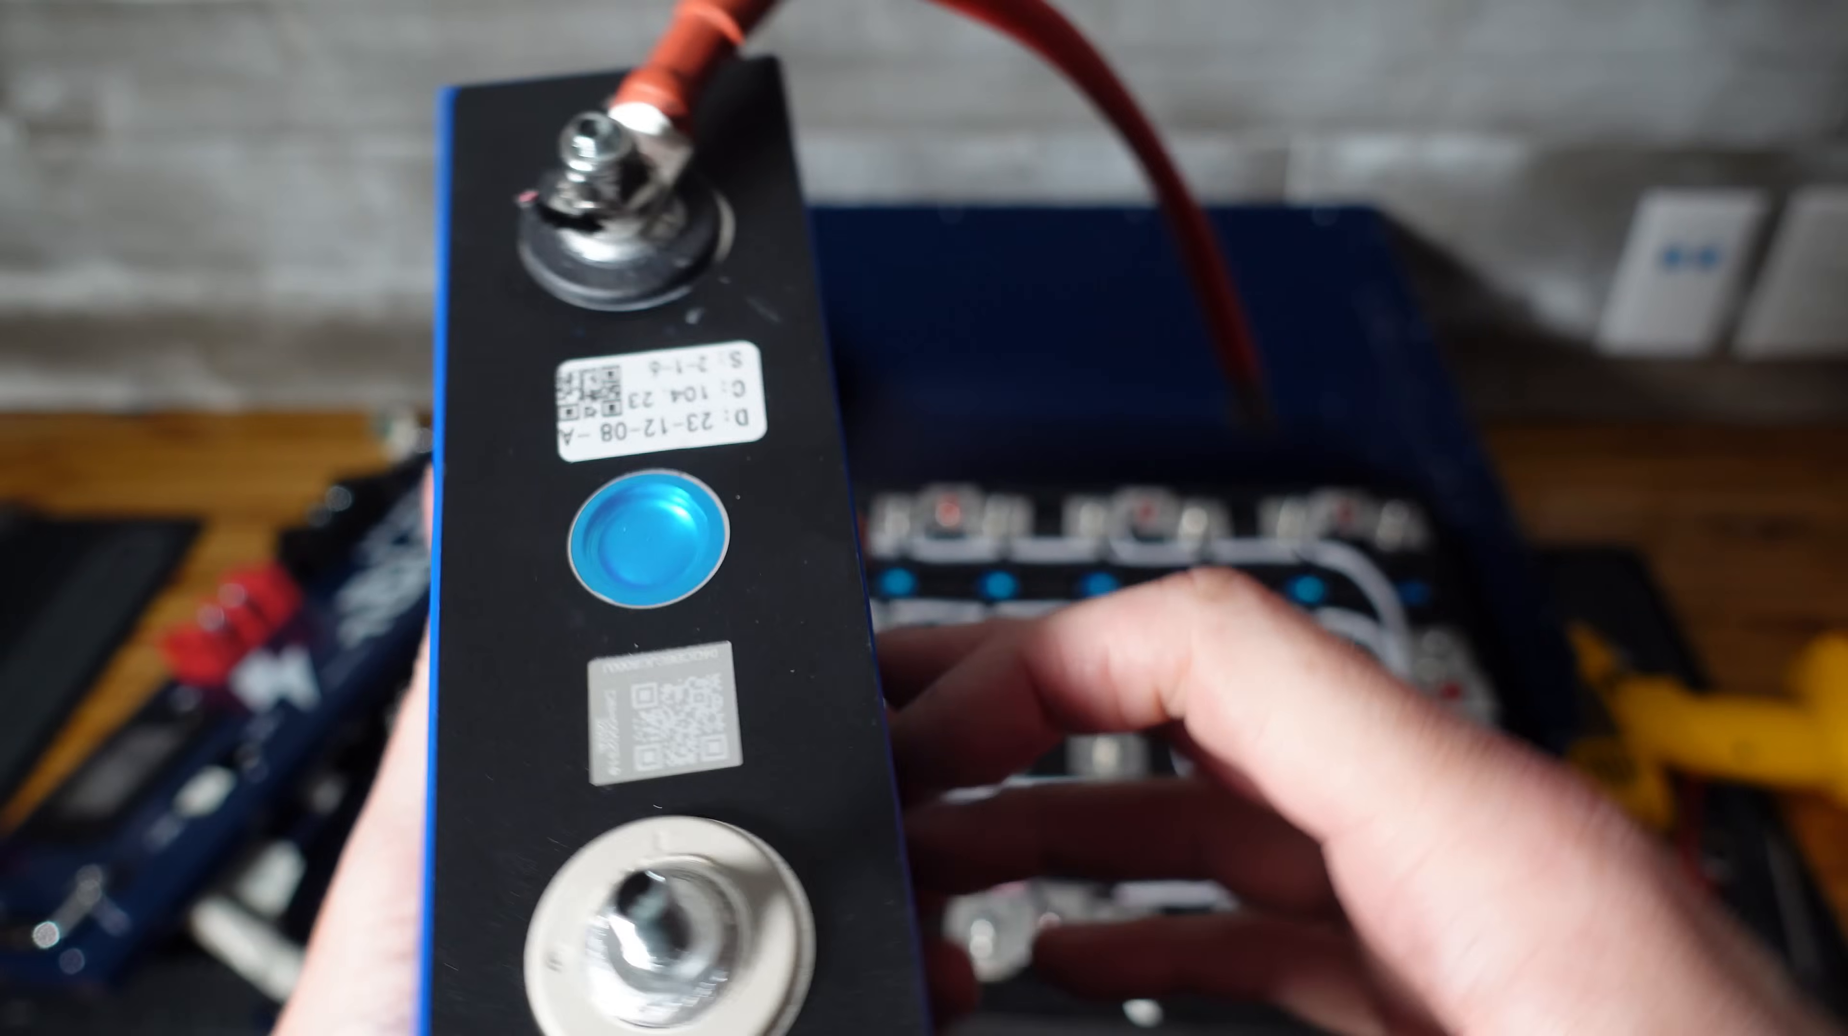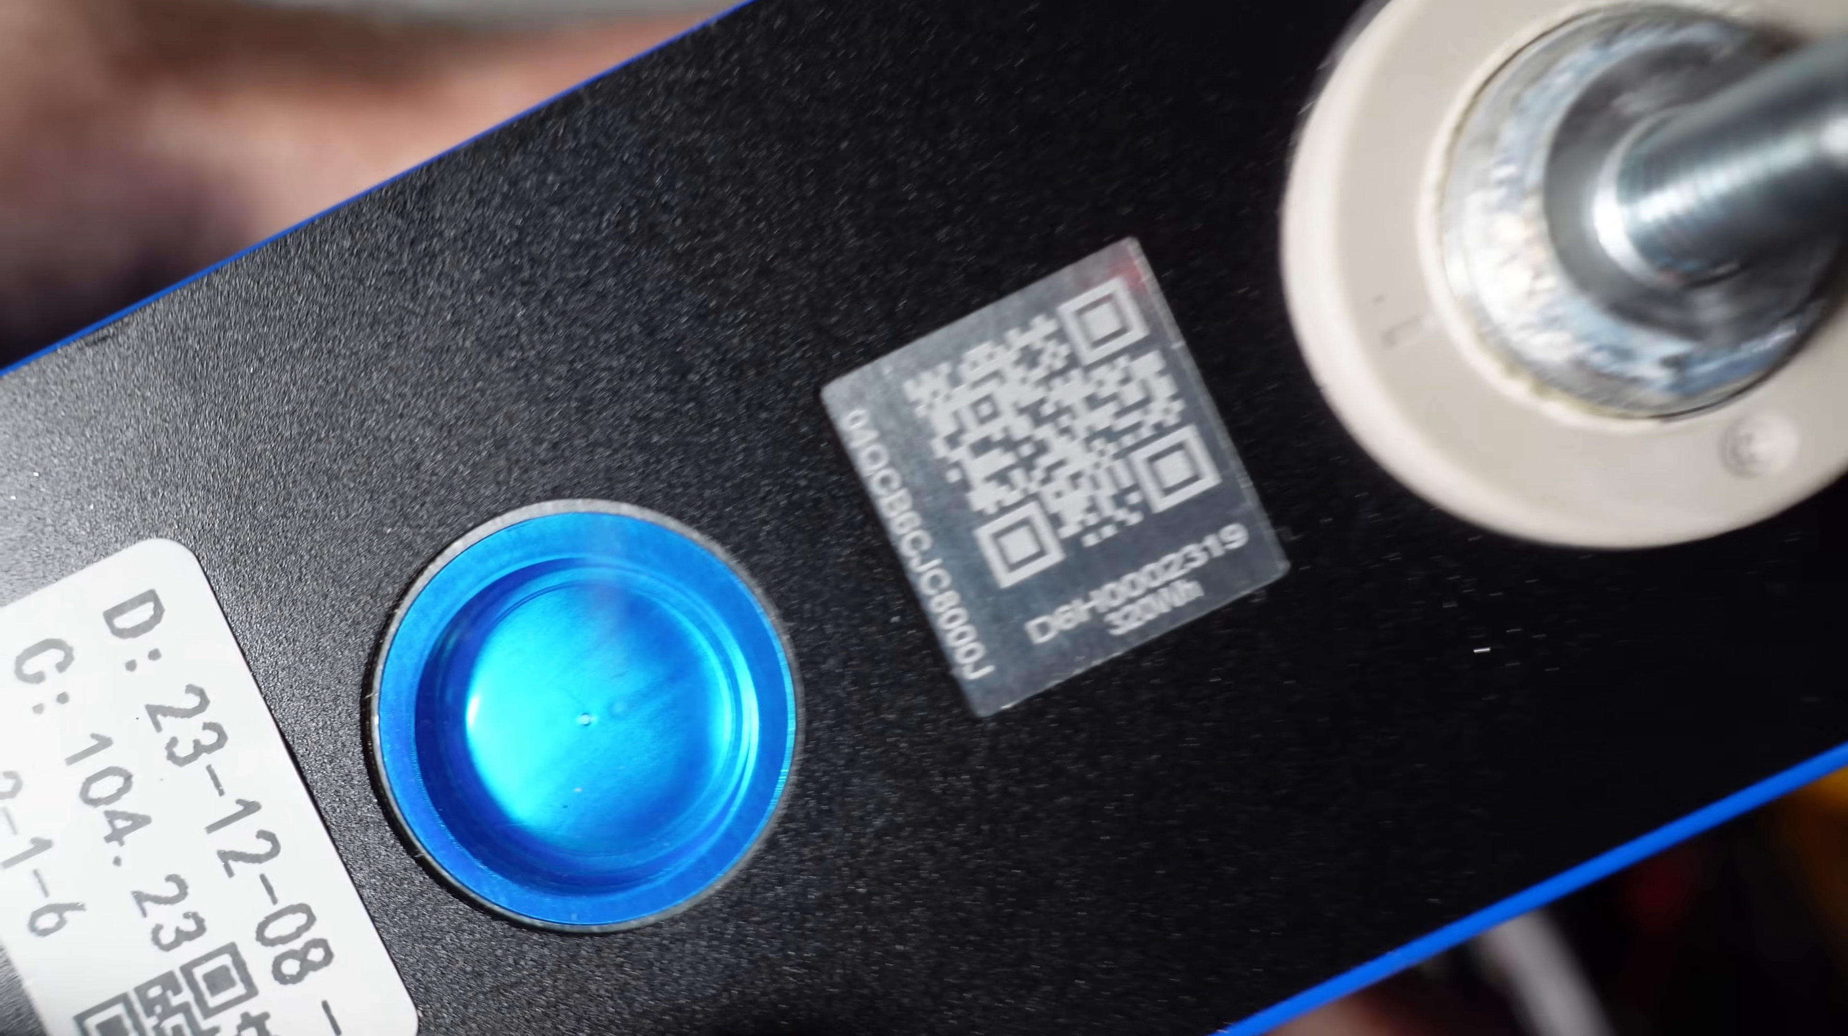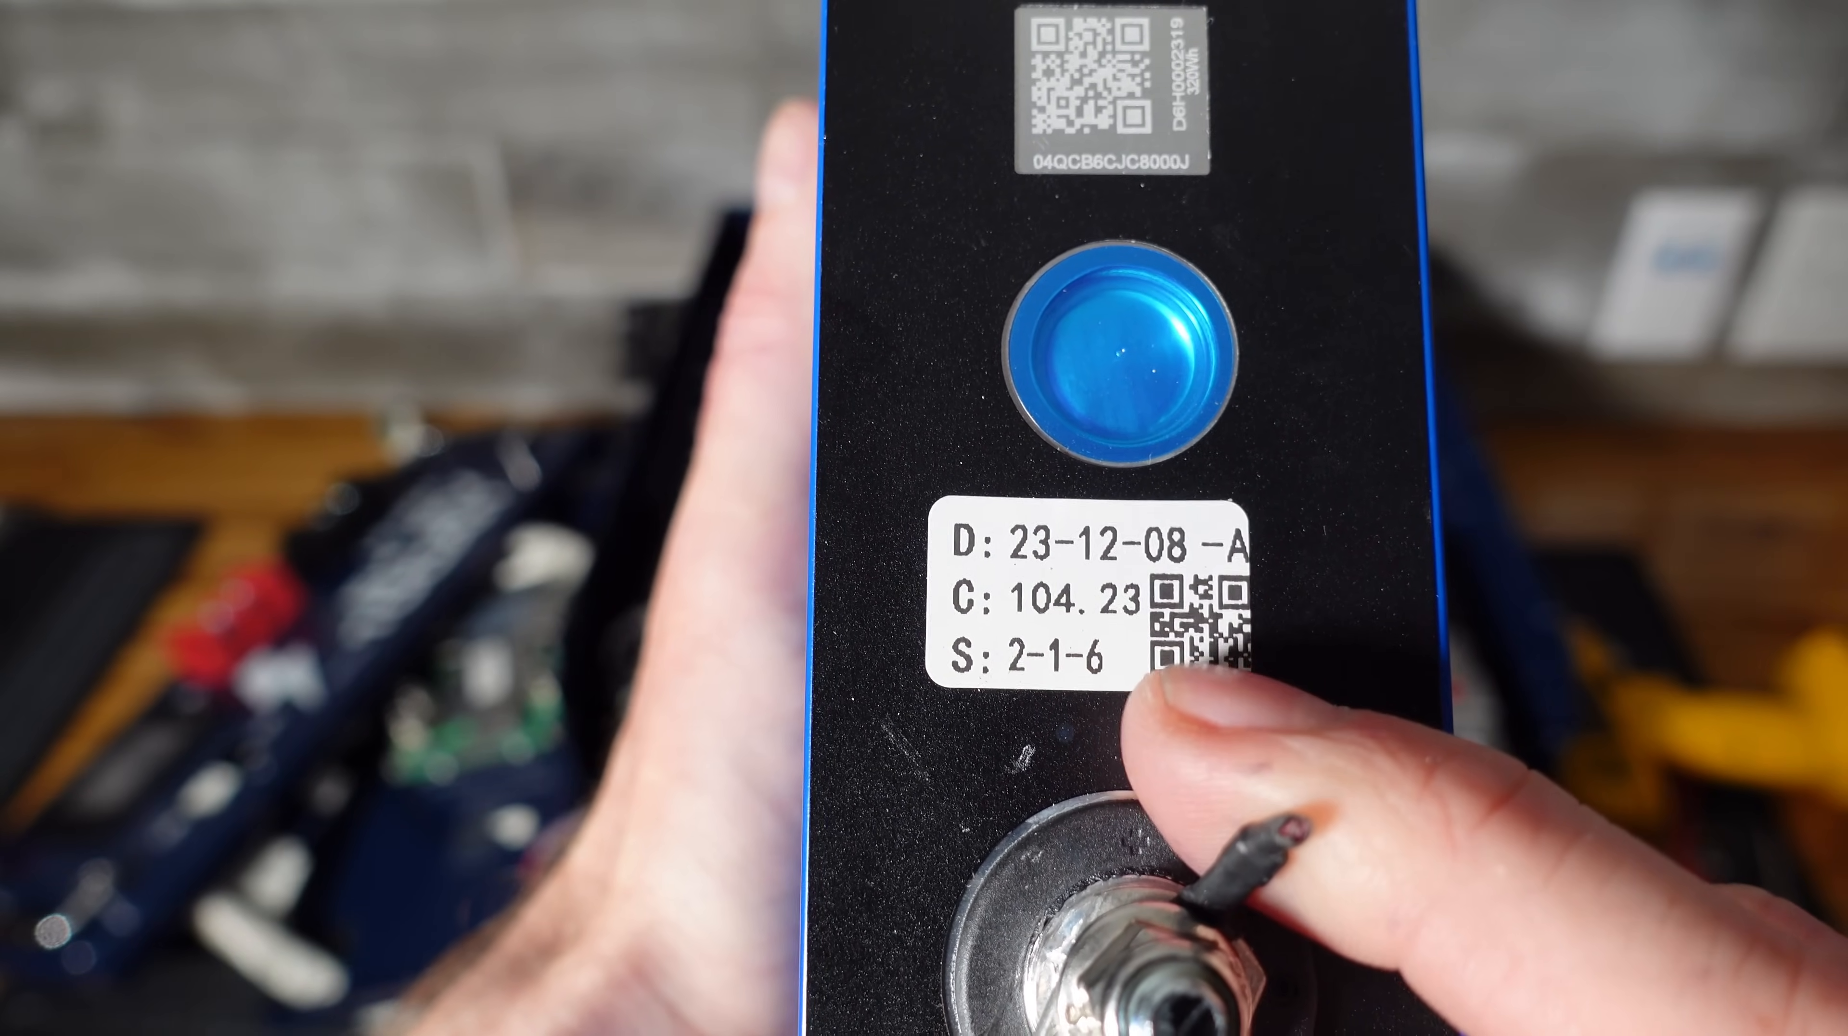These are EVE cells. They are EVE. I think they're LF100LA. So here is the QR code. You can see it starts with 04Q, which is typical of an EVE cell. It appears to be the original QR code. I don't see any sanding or polishing or anything that looks suspicious. And it says here 320 watt hours. So these are 100 amp hour cells. And there's a sticker on here with a test date. So I see December 8th of 2023. That's about four months ago now. And it tested at 104.23 amp hours.